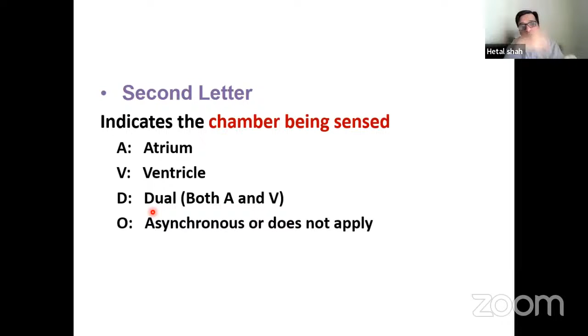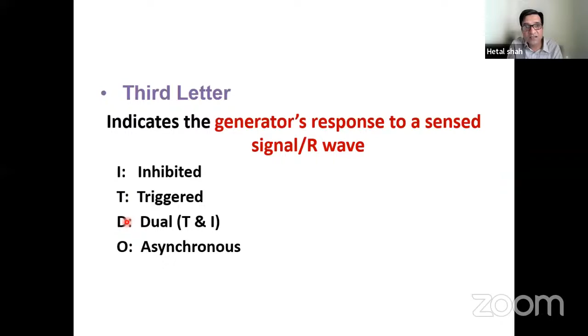So it could inhibit, that means I, or it will trigger the rhythm, or it may do the dual thing. The smarter generation pacemaker can inhibit or trigger, depending on the signal they will decide, or it will be O, which is asynchronous. So wherever the third letter is O, that means it is asynchronous. It is pacing fixed at a particular rate, while I, T, or D as the third letter will tell you that this is a synchronous kind of pacemaker, right? Like AOO, the atrium is going to be paced, there is no response to the signal which is coming, and it is an asynchronous pacemaker.